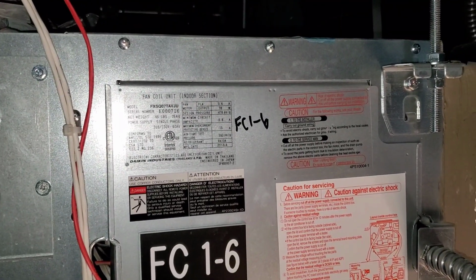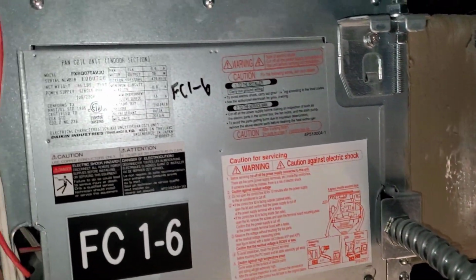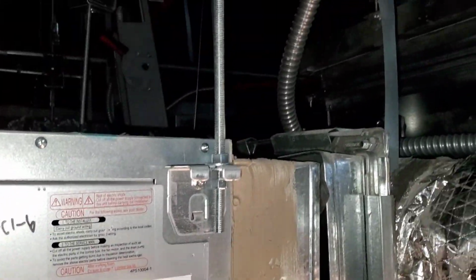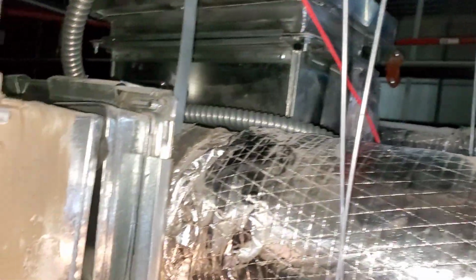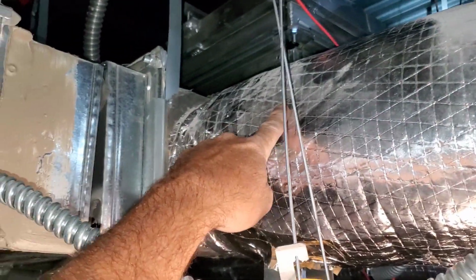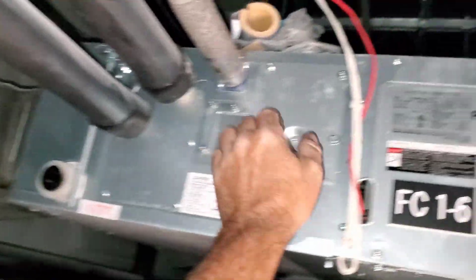the capacitors, it gets that high current surge, and I think probably have to power off for service or changing filters, or just whenever the power goes off, it probably just takes out these element fuses. But I believe there's supposed to be an air filter right here. There's no air filter. And there's outside air. Luckily, that's filtered up on the roof. Yeah, they're trying to kill these units already.